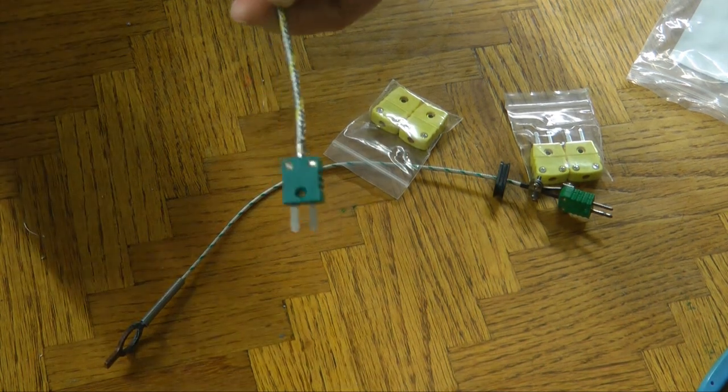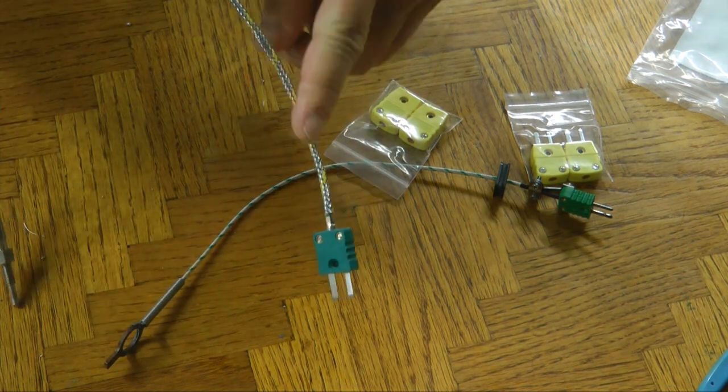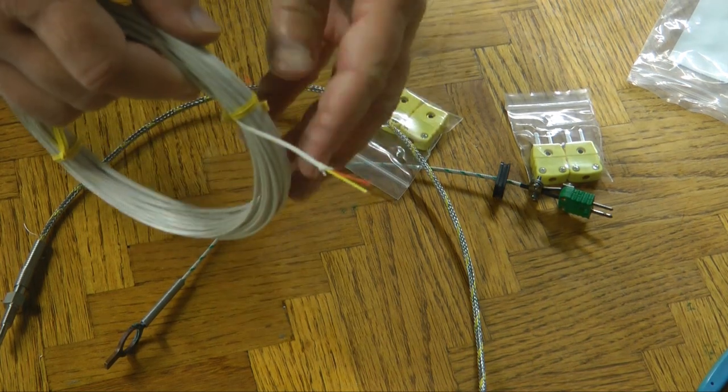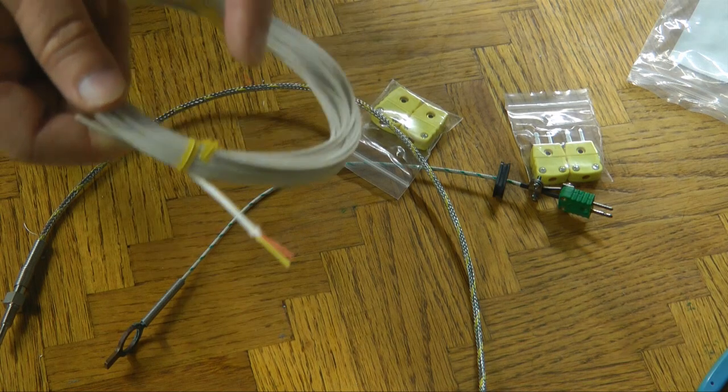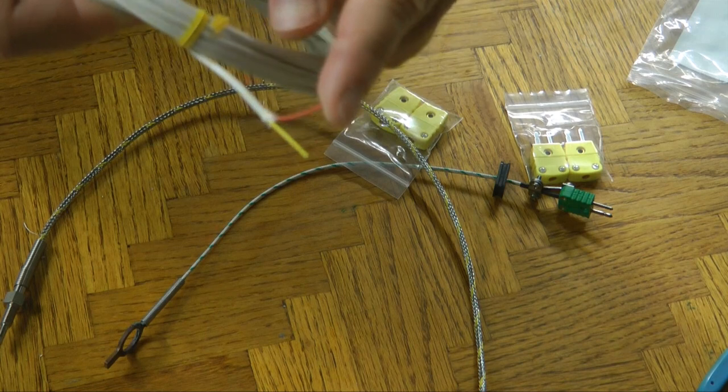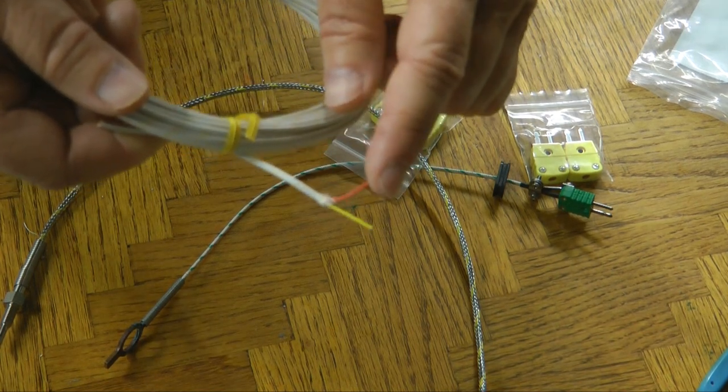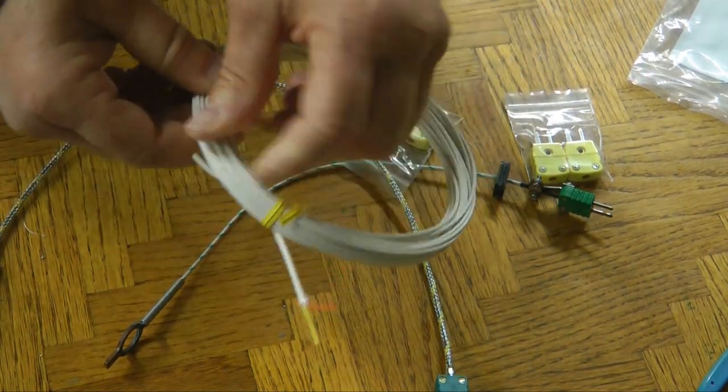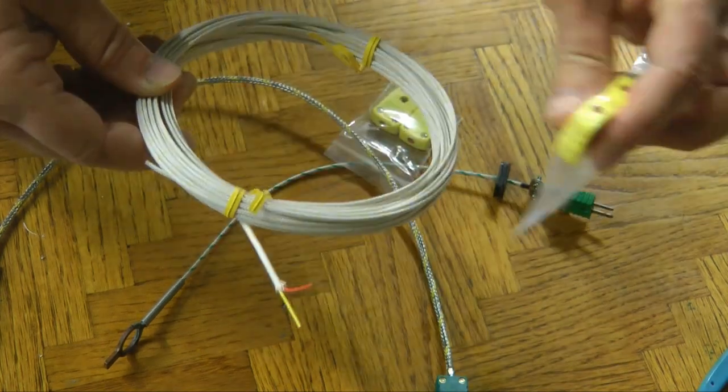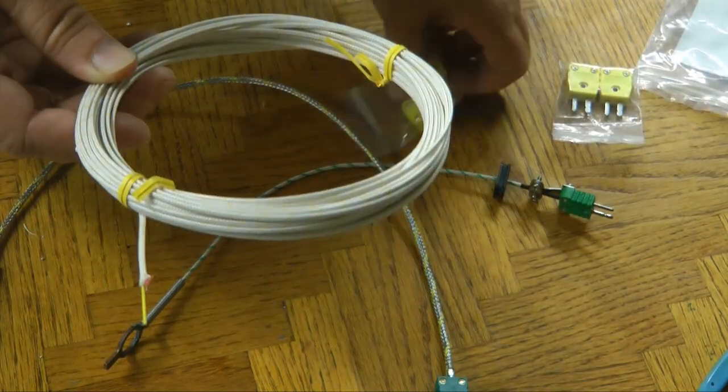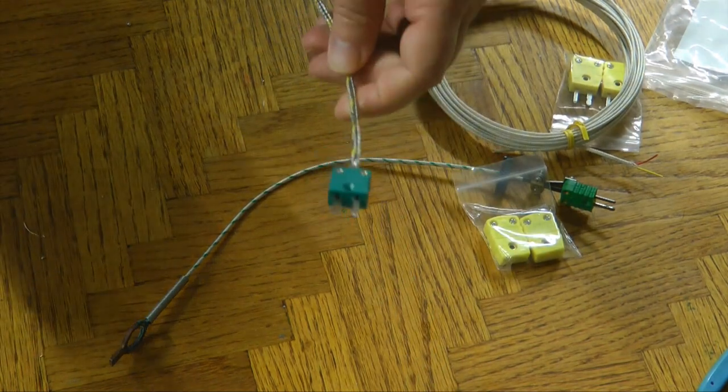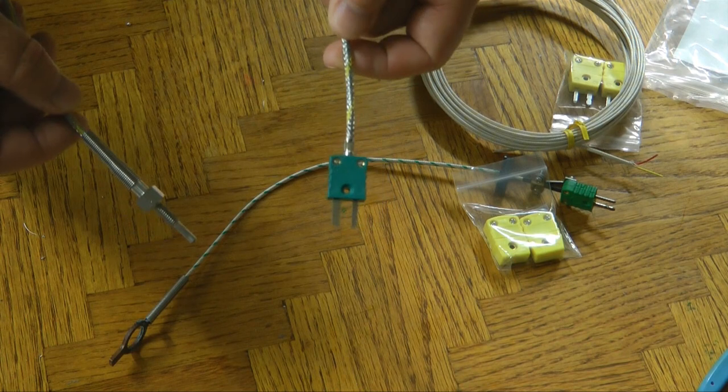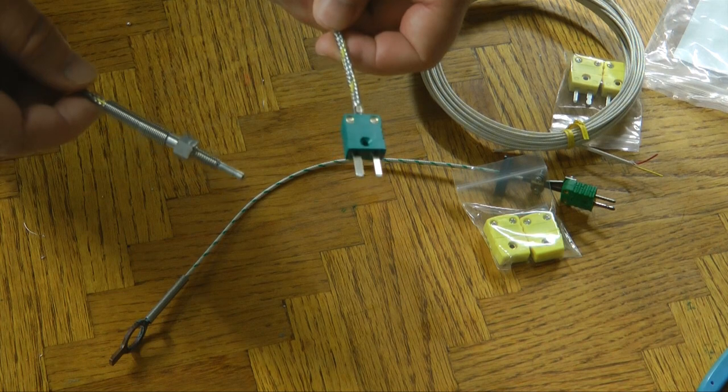So what do you want to do? You want to build an extension cable as long as you want but what type of wire do you want to use? If you're going to build a plug so that you can plug into this, the wires you want to use are, if this is a type K thermocouple which it is, you want to continue the chromel wire with chromel and the alumel wire with the alumel. So in other words to build a proper extension cable you need to get yourself some more of the alumel and chromel wire. Well guess what, just go to Amazon, buy it. This is basically a spool of, and they just call it type K wire because we know the ANSI standard for type K is alumel and chromel wire and again the color coating, the alumel is the red, the chromel is the yellow. And that way you can cut off as much or as little of this as you want for your extension cable, put on a male connector and a female at the other end, and now you can extend this all the way up to your instrument. So the moral of the story is if you're going to build extensions go right ahead, just don't use copper wire. If you use copper wire the thing will still work but the readings will be wrong.